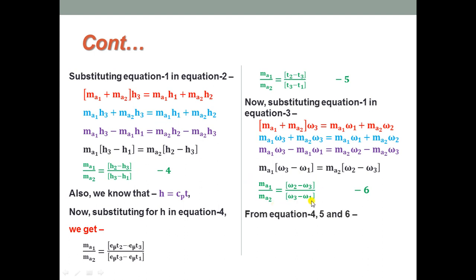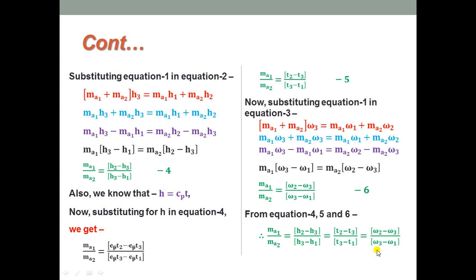So we can compare the ratios based on enthalpy, temperature, and moisture for adiabatic mixing of two streams: ma1/ma2 = (h2 − h3)/(h3 − h1) = (T2 − T3)/(T3 − T1) = (ω2 − ω3)/(ω3 − ω1). This is the complete comparison between different streams for an adiabatic mixing process.